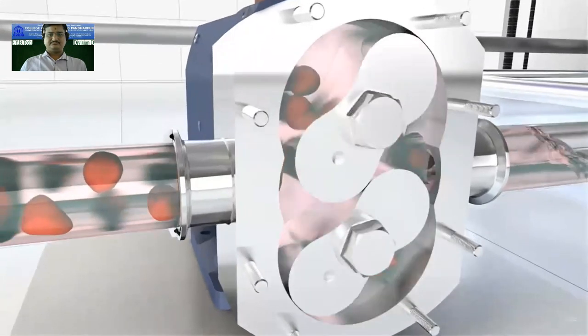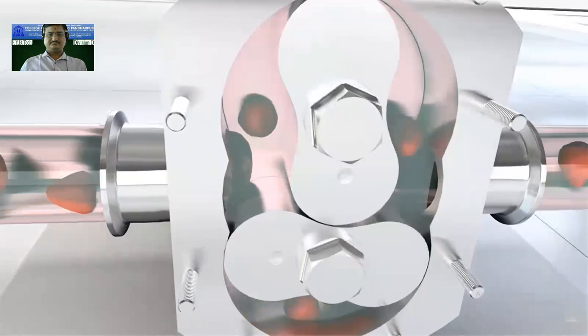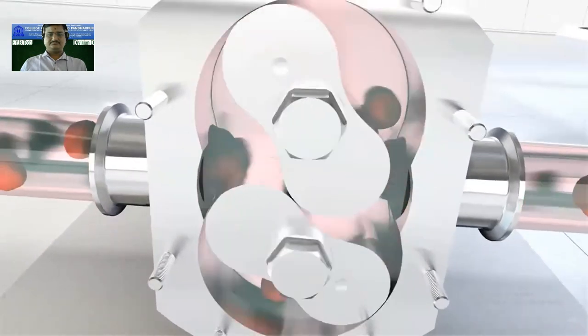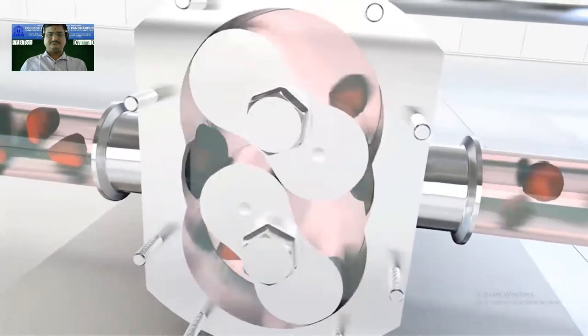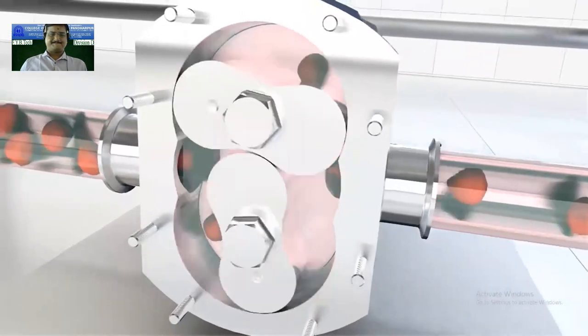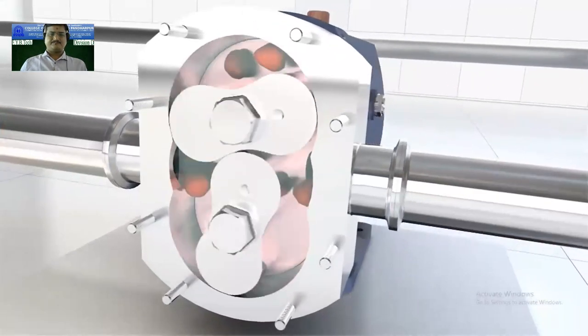For improved volumetric efficiency when transferring low viscosity liquids, the bi-lobe rotors are also available in non-galling alloy. This allows closer pump head clearance and reduced slip.